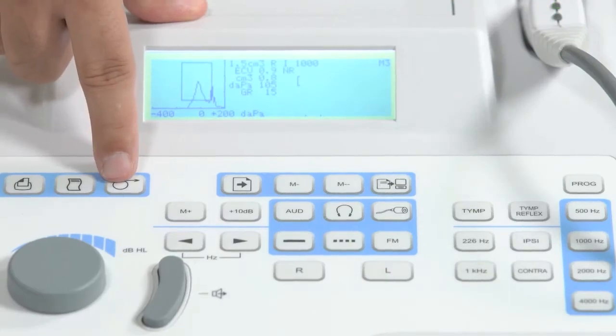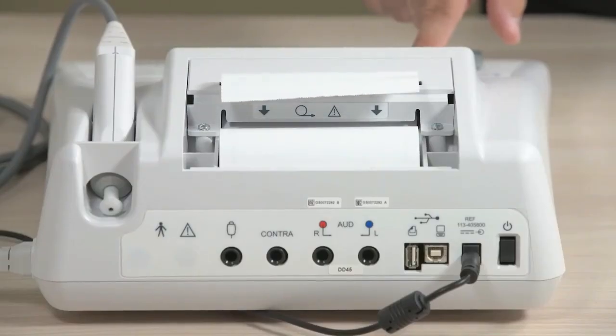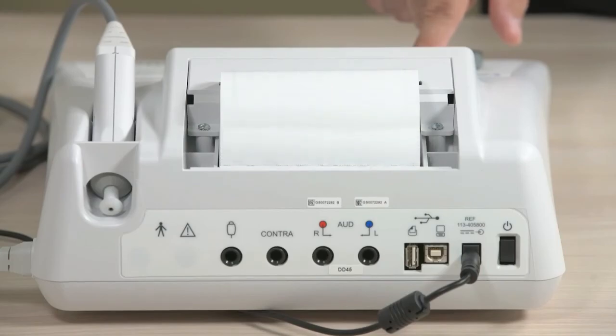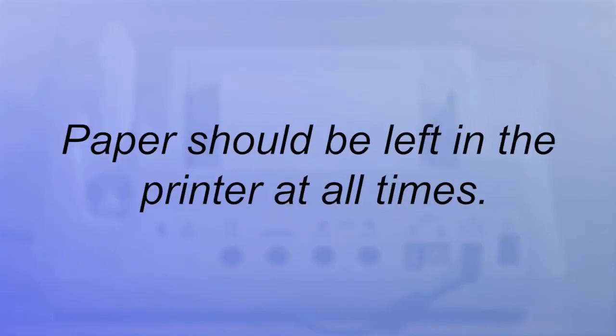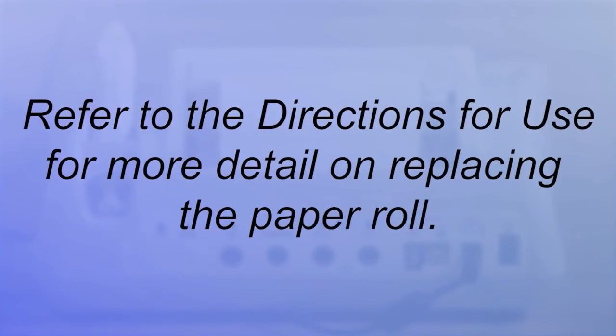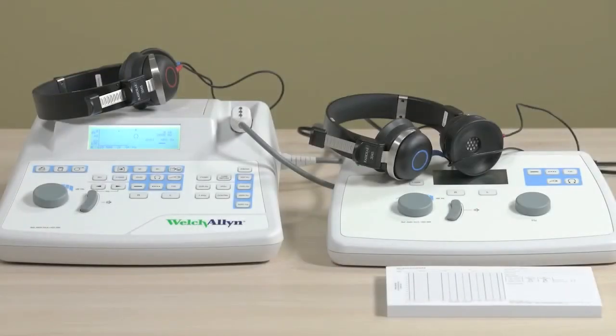Press the Paper Advance button until a section of paper is long enough to pass through the printer cover. It's important to note that paper should be left in the printer at all times, even when it's not in use, which prevents the print head from sticking to the roller. Refer to the directions for use for more detail on replacing the paper roll. Welch-Allyn recommends annual device calibration. Refer to your directions for use and other reference materials included with the AM282 audiometer and TM286 AutoTymp for detail on device setup and instruction.